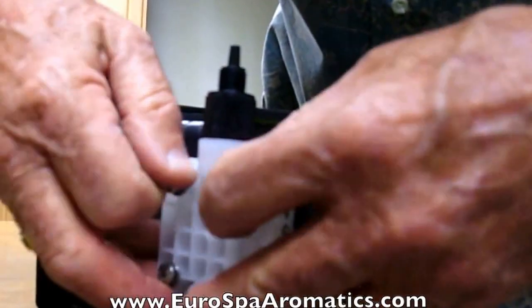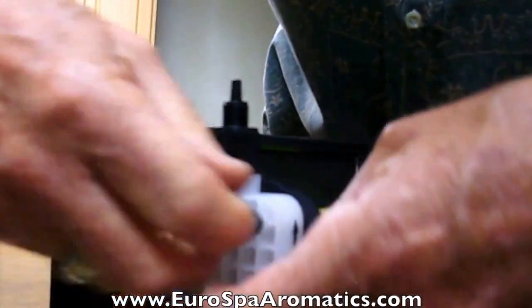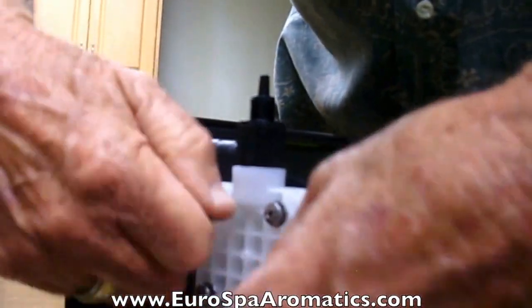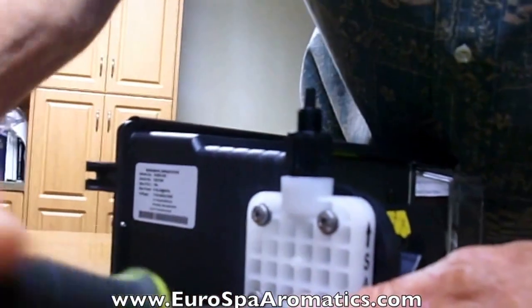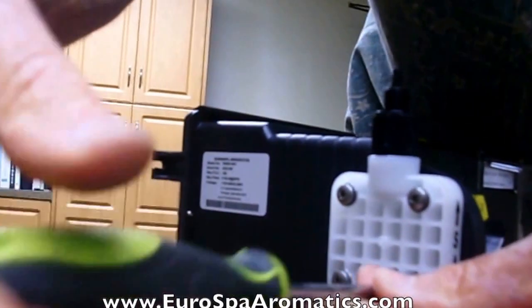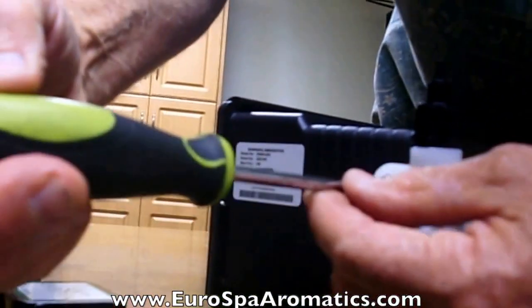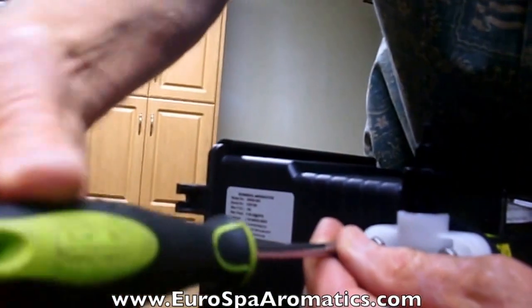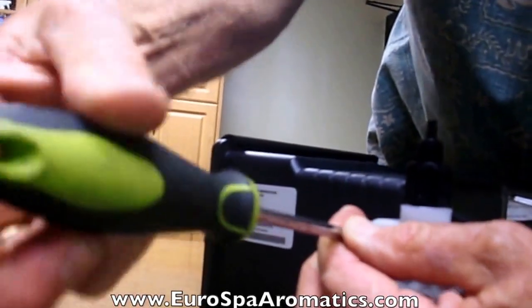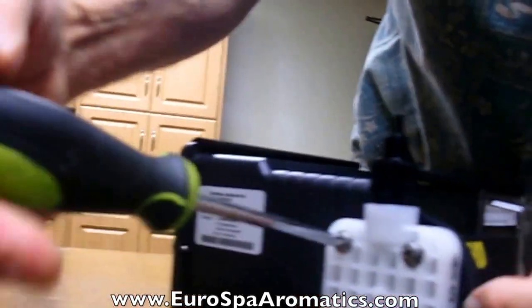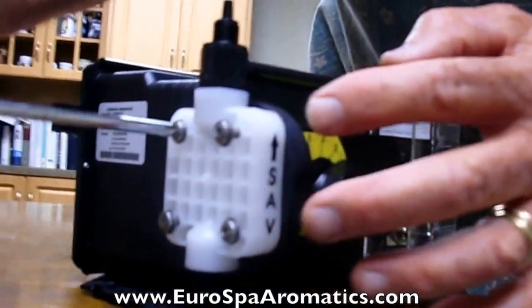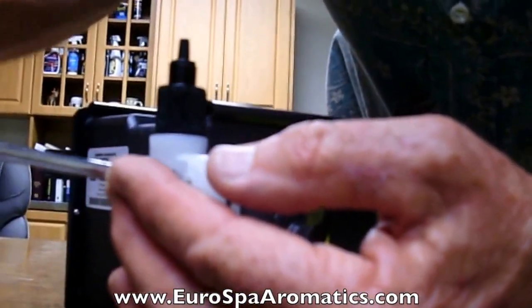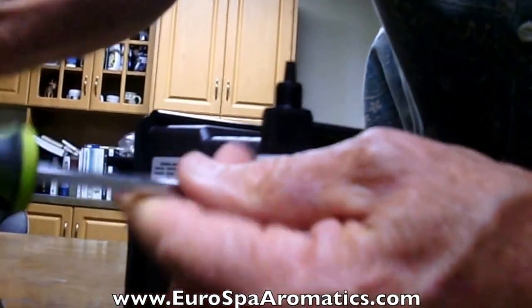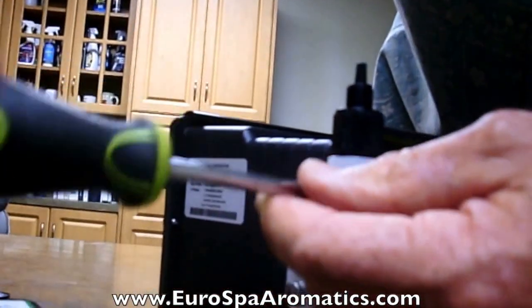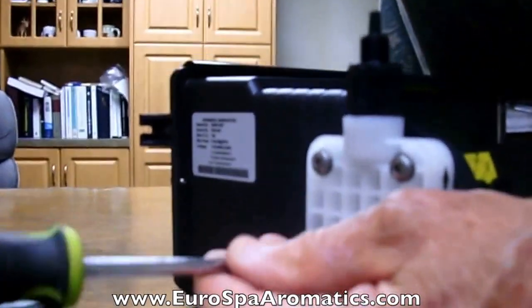The screws get started. And that's a little more important at this point to bring these screws down tightly in an opposing manner. So we'll just get it snug there, move up to the opposite corner, do the same thing, bring it down snug. Because as you do this, you're beginning to get a seal with the gasket from the pump head against the pump body. So you don't want to do this unevenly. You want to do it with even torque applied all the way around to keep the gasket from deforming.